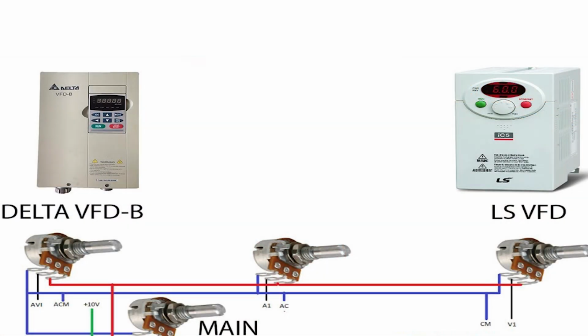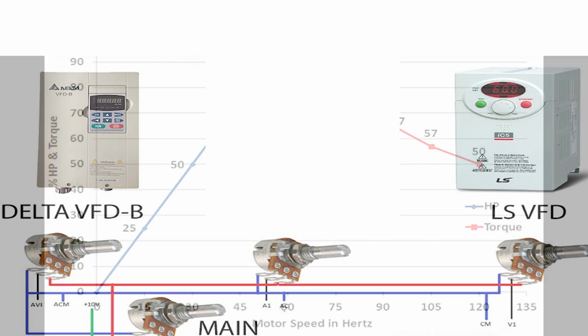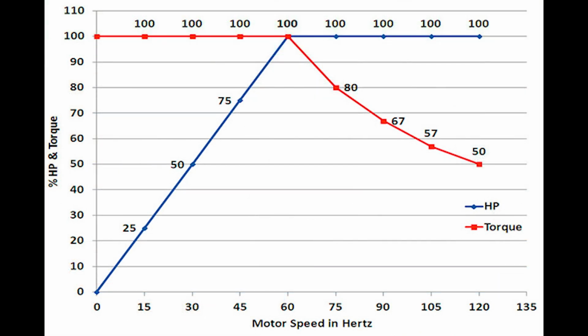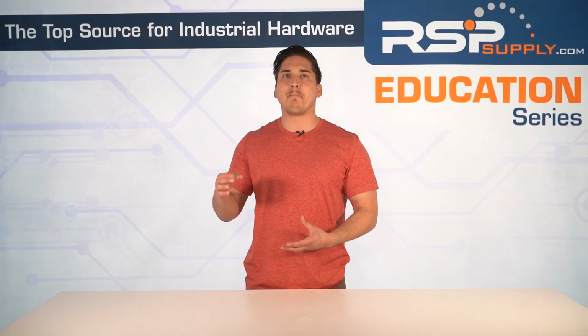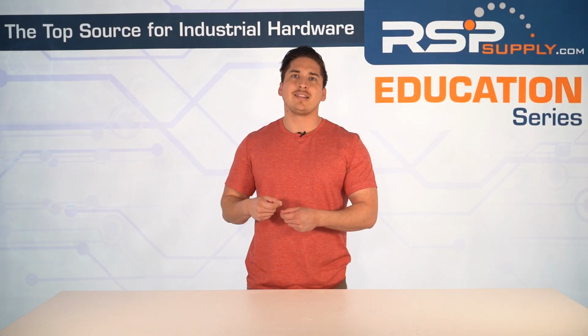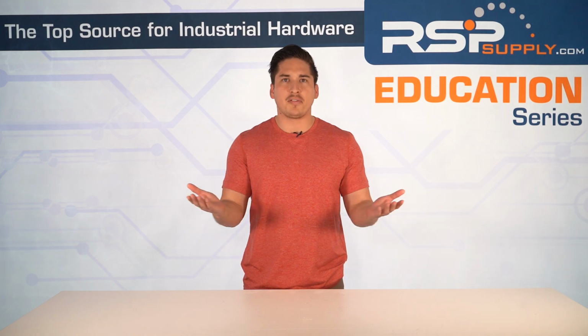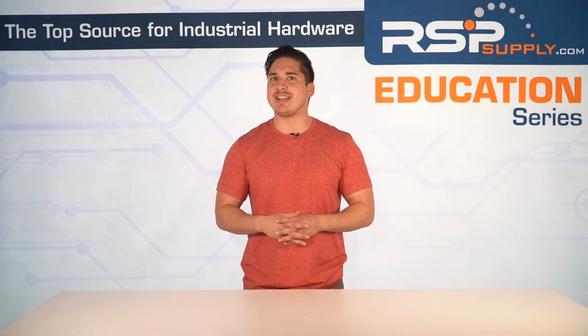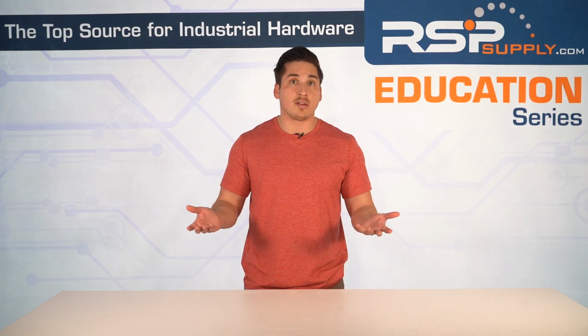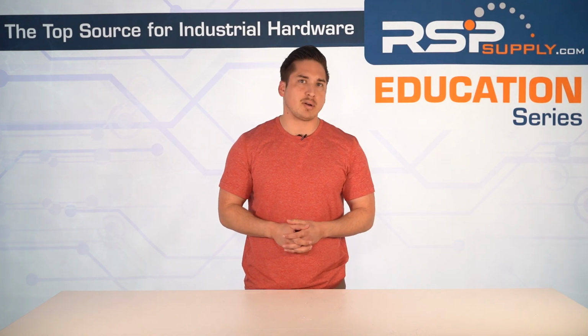We've got two VFDs synchronizing motors. So in a peer-to-peer network using Ethernet IP, a VFD is going to produce its speed and torque data. That's VFD A, for example. VFD B consumes that data to match its motor speed. Both VFDs communicate to each other without a PLC getting involved. What's the result? Faster response time, better synchronization.